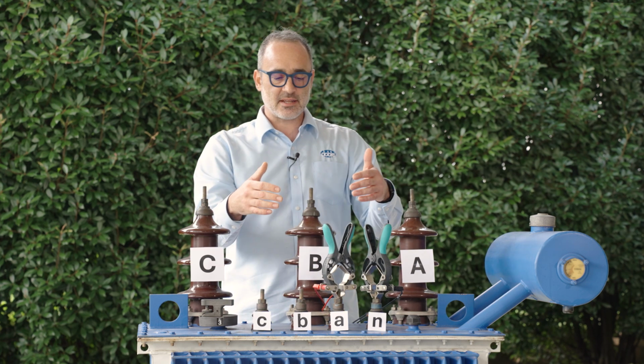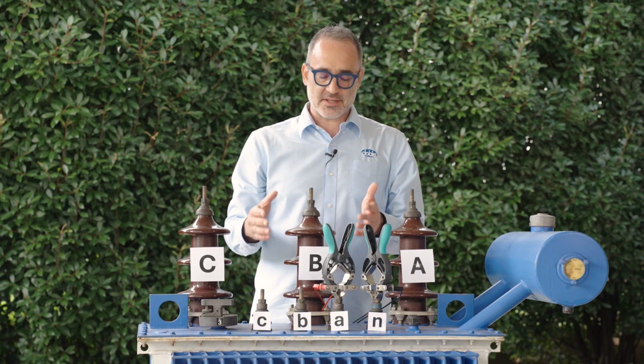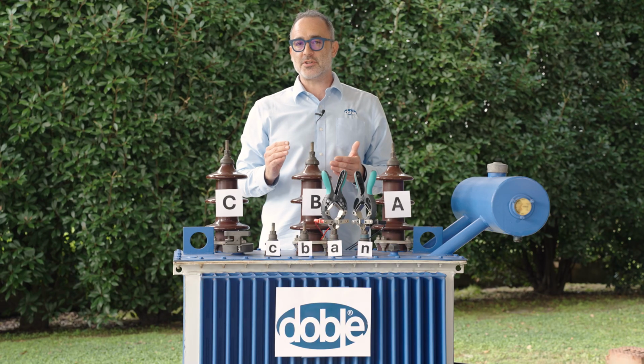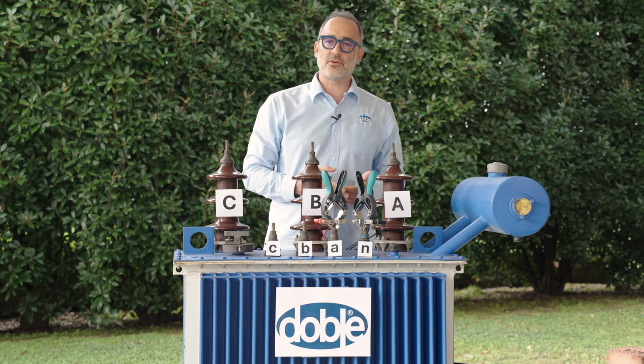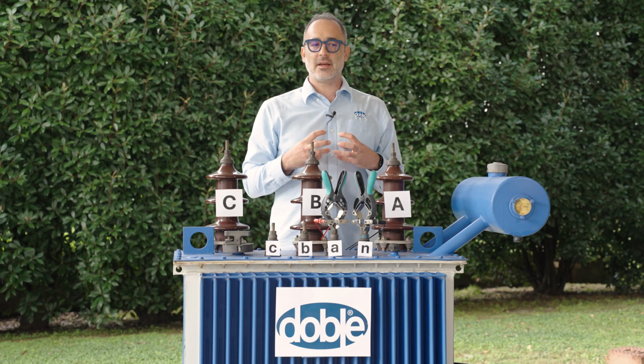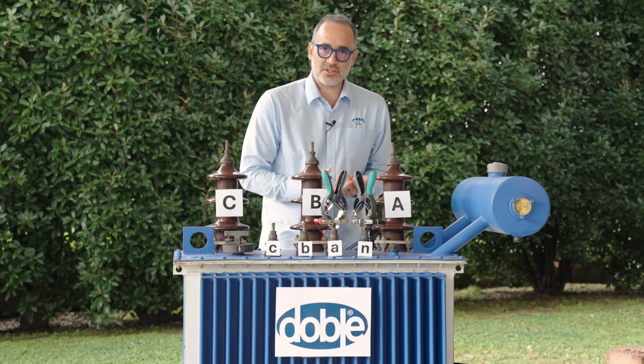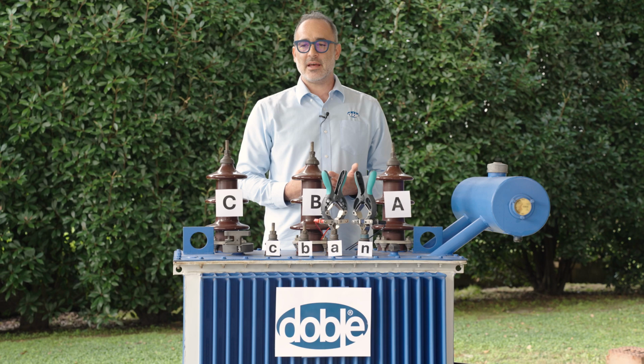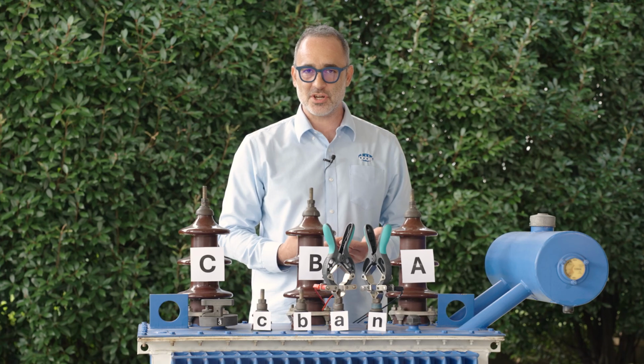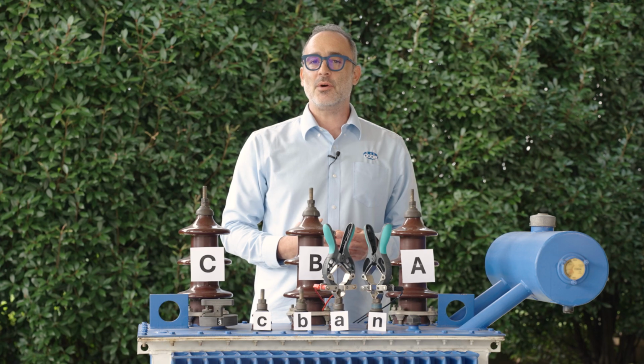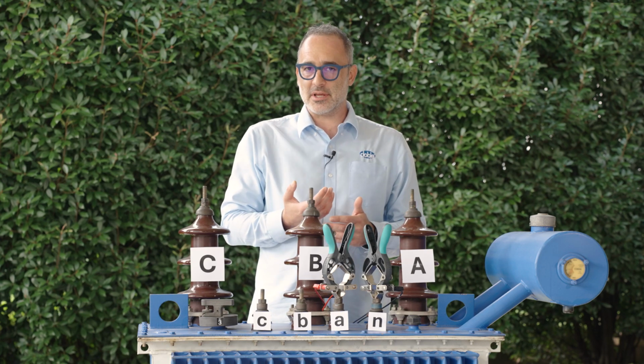Why does this test take longer to execute? Simply because when you're generating a certain current on the winding, it is basically against that change. The inductance of the winding is not allowing that change to happen. It's resisting the change, and that's why we can raise the current only slowly.